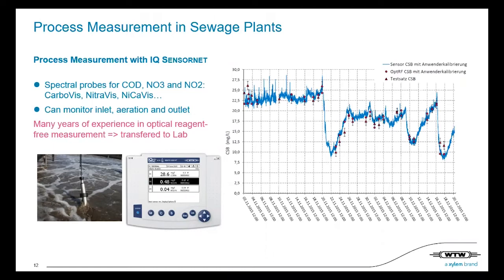And this is, if you look at the right side, you see the blue line, so this is the constant reading. With IQ SensorNet, you can monitor inlet, aeration, and outlet. Now, this experience has been transferred to the lab, and I have to say, with the spectrophotometer, we can only cover the biggest part, meaning the successful cleaning process, so we can measure the outlet.